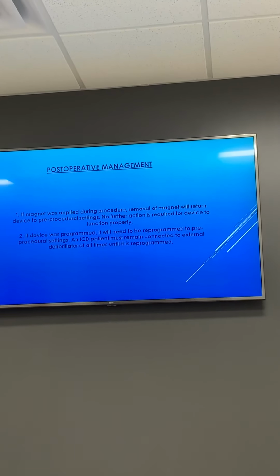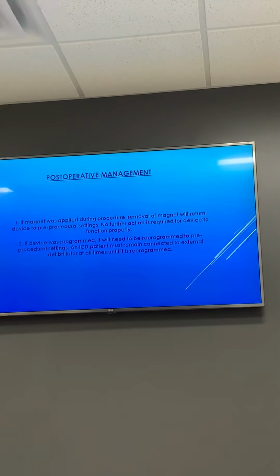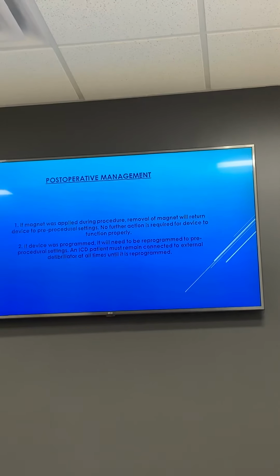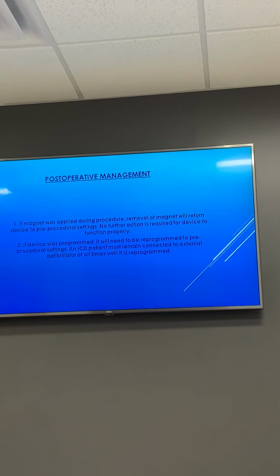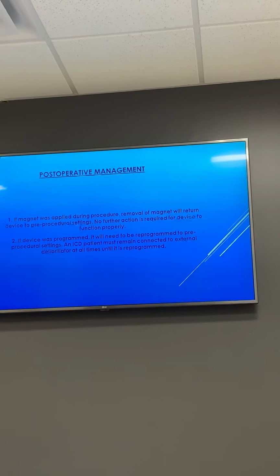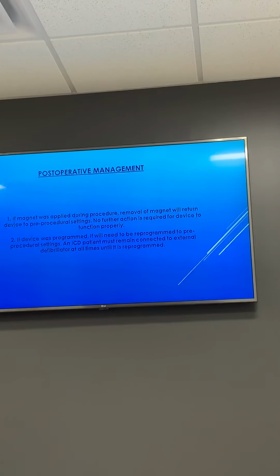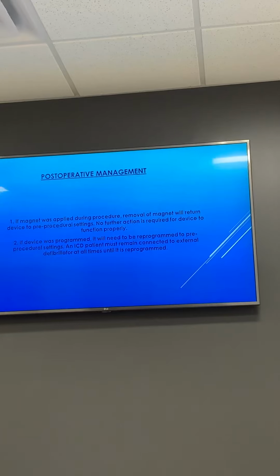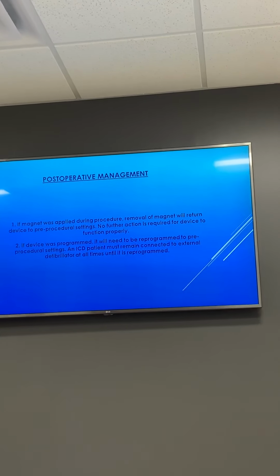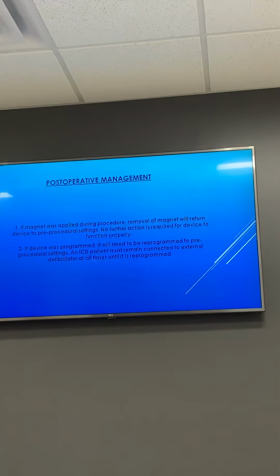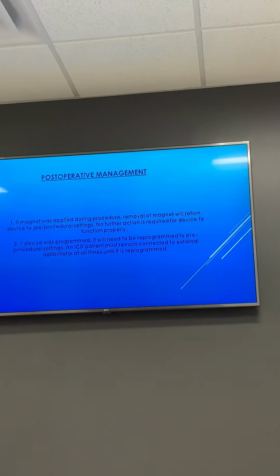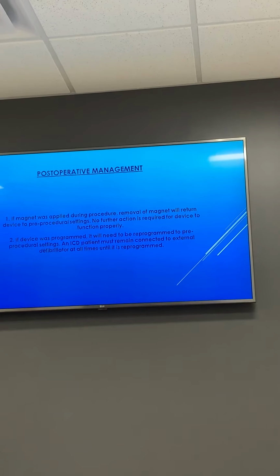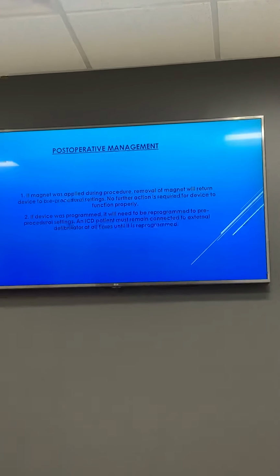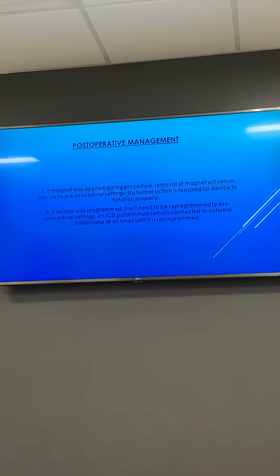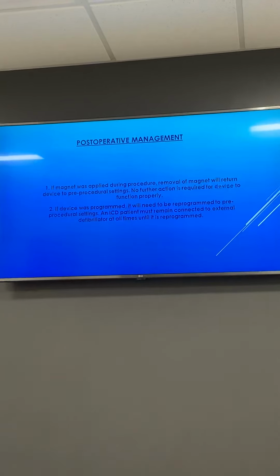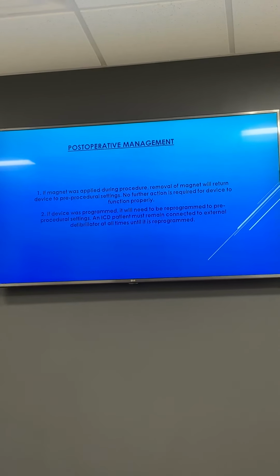If the device was programmed, when they come out to you all, they will need to still be hooked up to the external defibrillator until the device is programmed back on. Pacemakers, not so much, just because they don't need the external, but they'll still need to be programmed back to their pre-procedural settings to get back to what they were when they walked in. Most of the time, if a rep's coming in to program, they'll go ahead and run a device check as well. Is that done in PACU or phase 2 or both?